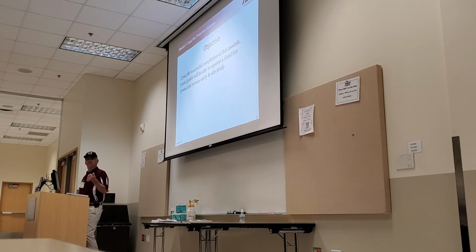The halon systems, when it discharges in a room, it has to be completely out of the tank, through the pipe, and out of the nozzles in 10 seconds. So a room like this would probably take about 1,200 to 1,400 pounds of halon to protect this room as a computer room. So this stuff flies out of the pipe. I've heard it blow walls and stuff like that. But you have to do room integrity tests too on that. So, move on.